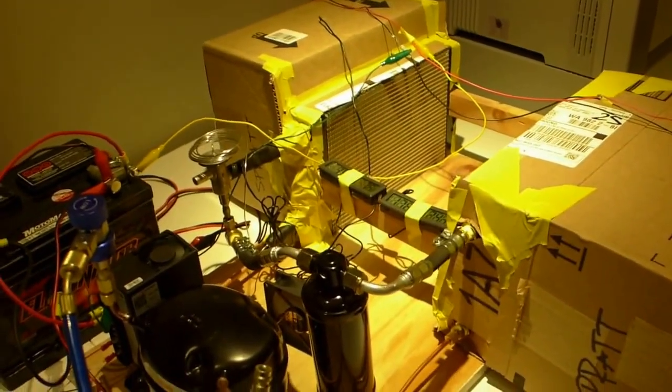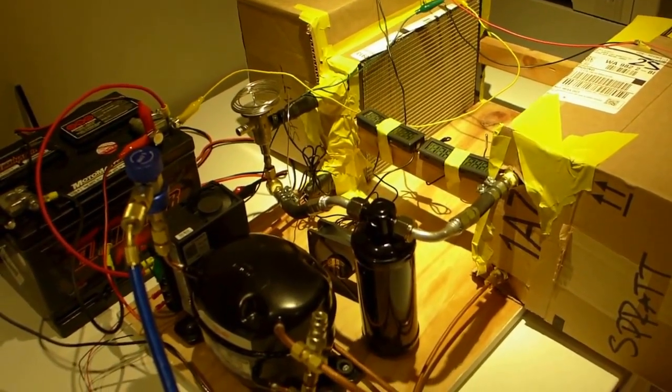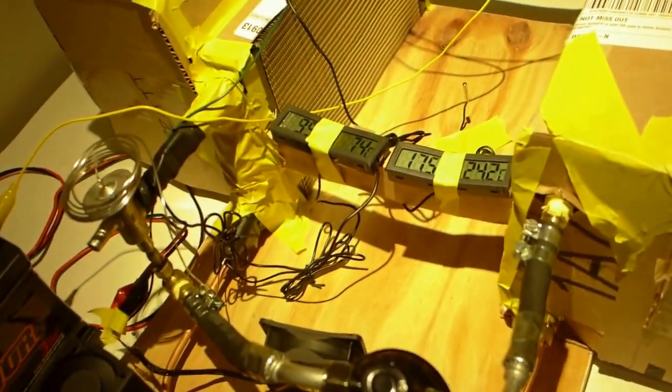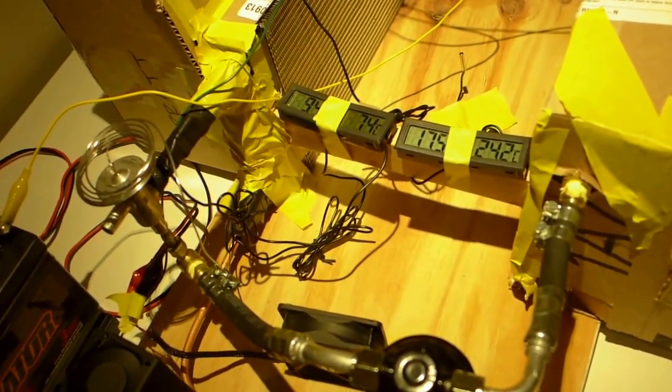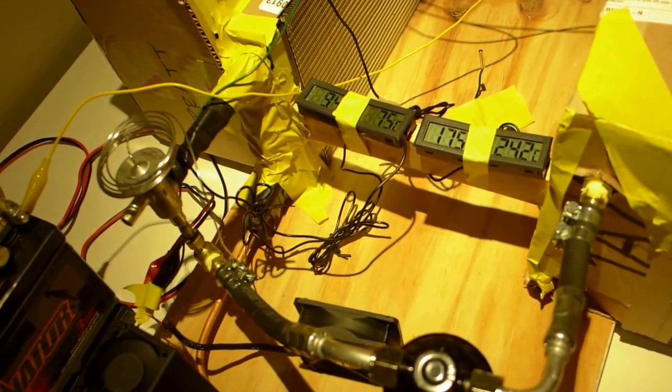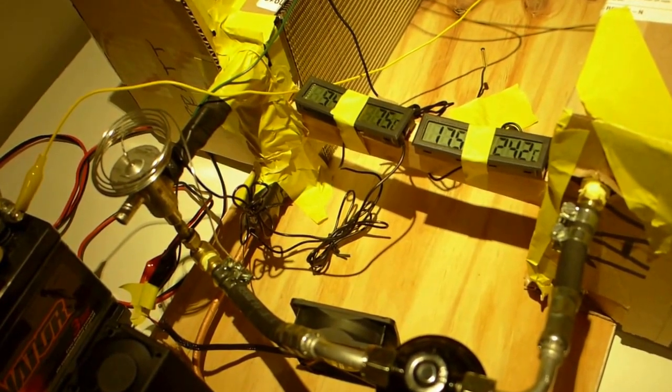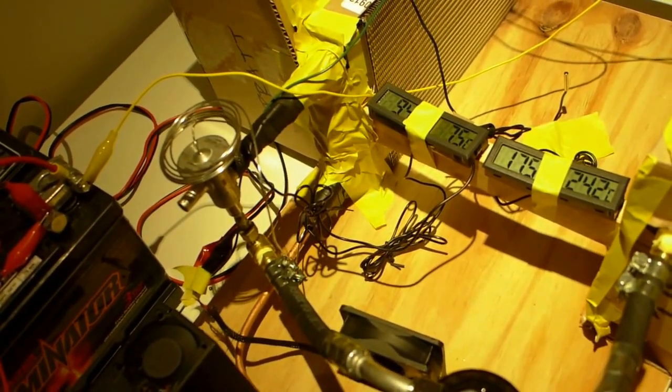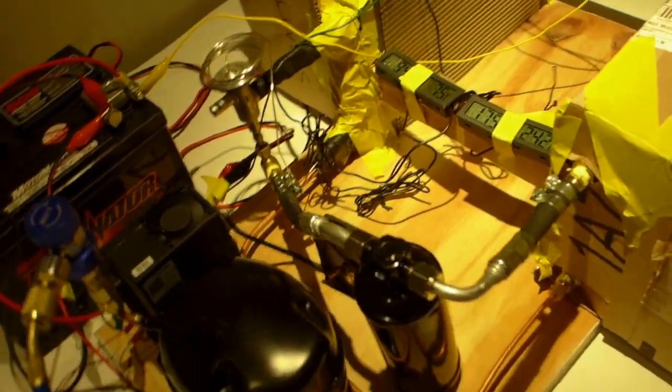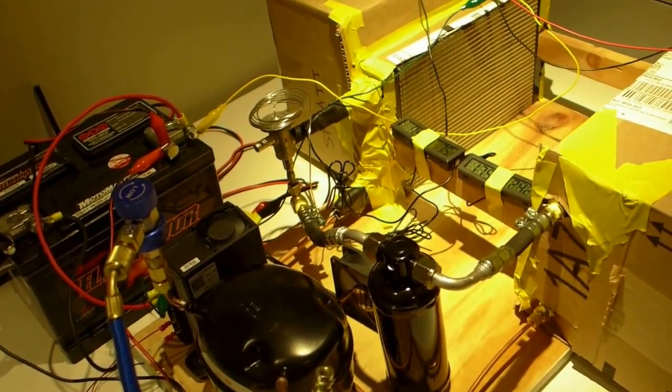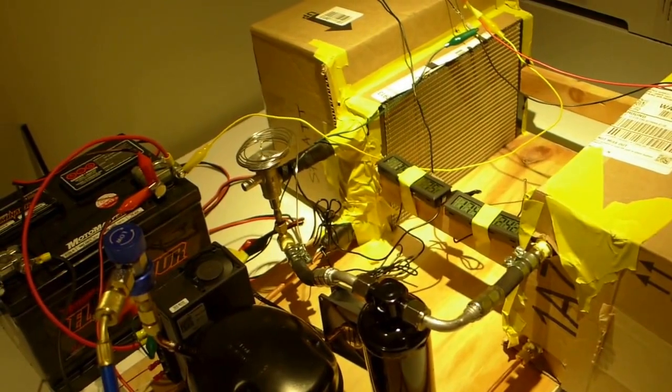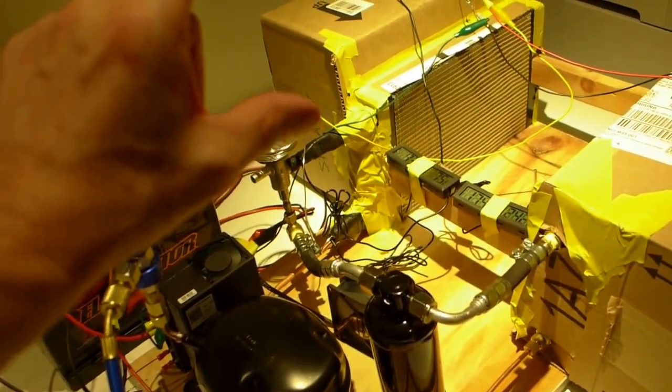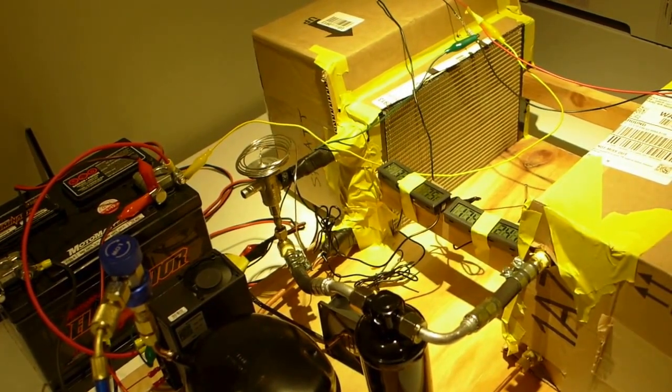Now, that's pretty much it. I mean, I've cooled everything down and squeezed another 0.2 degrees C out of it. So a little under seven degrees Celsius difference. So see right now where we're sitting is air temperature 24.2 on the far right. Outside, the outgoing temperature is 17 and a half degrees. So it's nice and cool air that's blowing out. And then the other two temperatures are the input and output of the evaporator. So it's quite an odd relationship. As you put more charge in the system, it's flowing through. Greater mass of refrigerant is being pushed through the system. And so the differential temperature across the evaporator sometimes is less than you would think it would be, but it's flowing much, much more. So it ends up being more energy removed from the air.